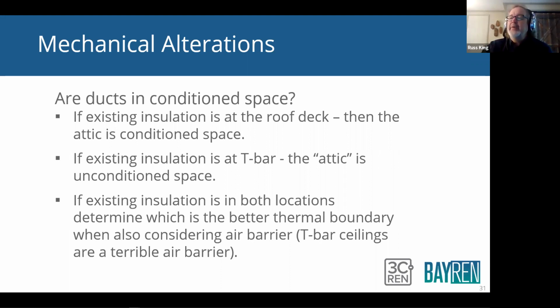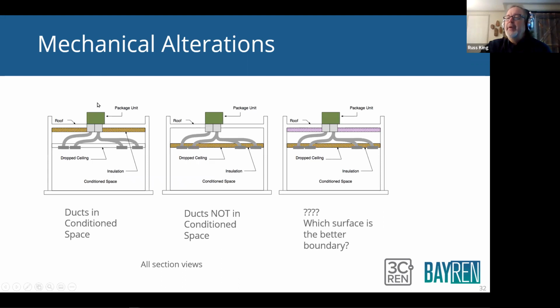Okay, so I got some diagrams here to explain that. So here's your rooftop package unit. Here's your insulation at the roof, and your ducts are down below it. These ducts are in conditioned space because this attic above the ceiling is more like the conditioned space than it is like outside. But if we take that insulation and move it down to the T-bar ceiling like this one, now the ducts are above the insulation, so this attic is considered unconditioned, right?